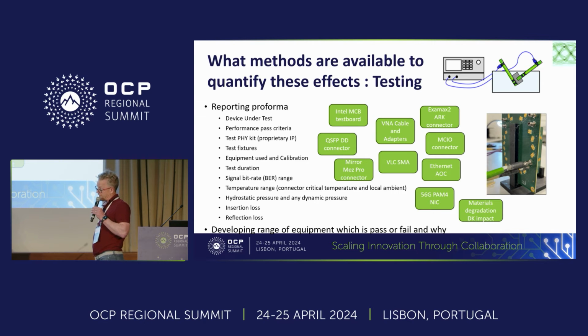Within the community, which we've had over 1 year's work, we have had many examples of equipment vendors showing their testing data for immersed connectors, cables, PCBs, DIMM modules, all kinds of things, and it's a really rich set of data that we have. And through that, we're developing methods for testing, for immersion equipment, and methods of reporting. So on the left-hand side, you can see the scope of the documentation that we are trying to converge on, how we ask people to share and record data on their testing.